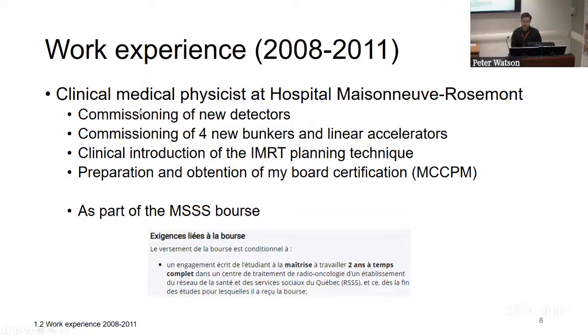And we worked a lot on commissioning of these new detectors, commissioning of the bunkers and the linear accelerators themselves. And when you do all of that together, you realize that it's actually very difficult to know if it's the chamber that is faulty, the cable, the electrometer, or the LINAC that is not set up properly. And it's a circular pattern that you have to figure out, which one is at fault, right? Because it's everything at the same time.